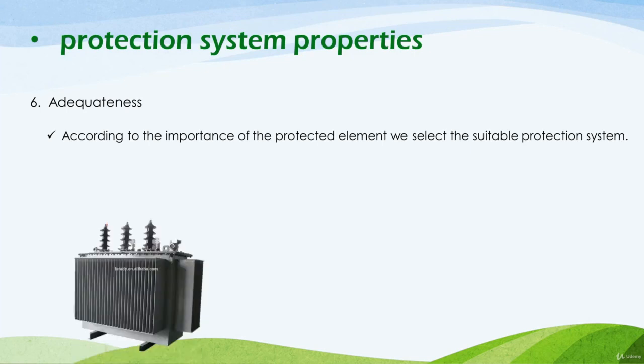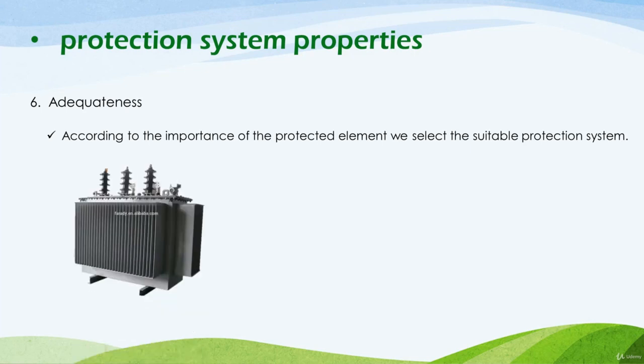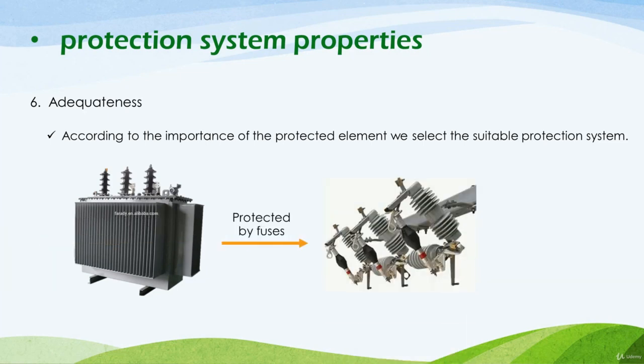For example, the distribution transformers, as we said, are elements that we need to protect. As the distribution transformers are not a very important element in the power network, we will use a very simple protection device, which is the fuse. Here we use an ordinary and simple protection device, the fuse, as the protected element itself is not a very important one. Alright.